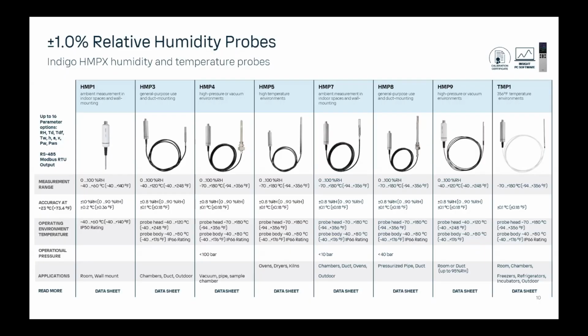So starting on the left, that's our fixed probe design, the HMP1. That's great for room, wall mount, anything that's not rated for washdown but still needs high accuracy. And then moving along, everything else is rated for washdown except the HMP9 on the right. So similar design, but we have the HMP3 still integrating with the Humicap sensor, but it has a cable itself and has a higher temperature rating. And then down the line, we have specific probes for high pressure and vacuum environments, high temperature environments in the HMP5, and high humidity environments in the HMP7.